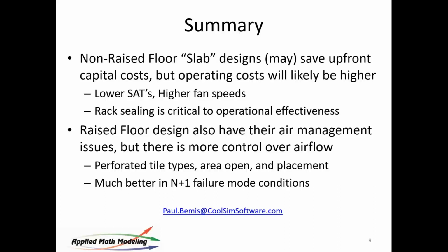So Murray had a question: if the IT provider has the ability to override the control on their internal fans, is it a value input for modeling? It can be. It can be, because we're making assumptions about the amount of air required by the server. So if there's a way to control that, and of course there is, you can control in some cases, on some machines, you can control the amount of air that's going through the device.